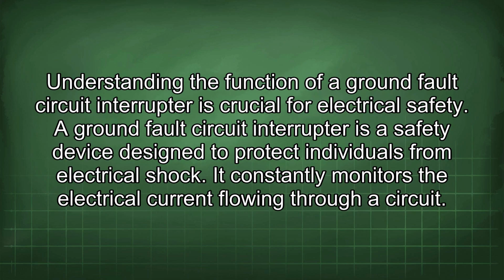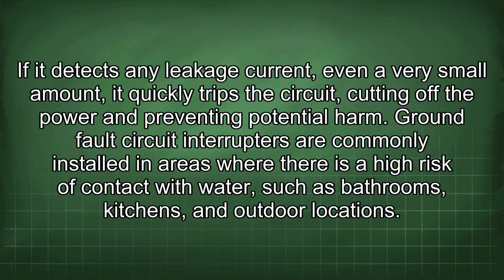Understanding the function of a ground fault circuit interrupter is crucial for electrical safety. A ground fault circuit interrupter is a safety device designed to protect individuals from electrical shock. It constantly monitors the electrical current flowing through a circuit. If it detects any leakage current, even a very small amount, it quickly trips the circuit, cutting off the power and preventing potential harm. Ground fault circuit interrupters are commonly installed in areas where there is a high risk of contact with water, such as bathrooms, kitchens, and outdoor locations.